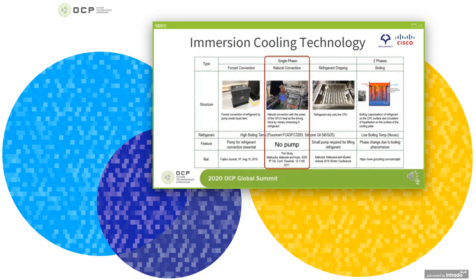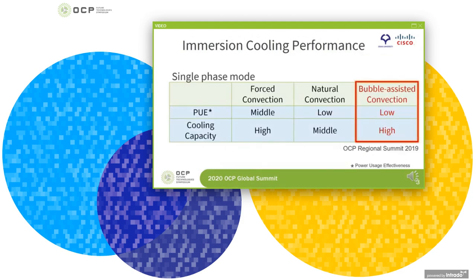We employed one of the single-phase modes, the natural convection method, which requires no pump but instead uses the force of upward flow of refrigerant generated by the heat from the CPU. We also added the support of bubbles. As we reported last year here, with this method, high cooling characteristics were achieved while securing low PUE.